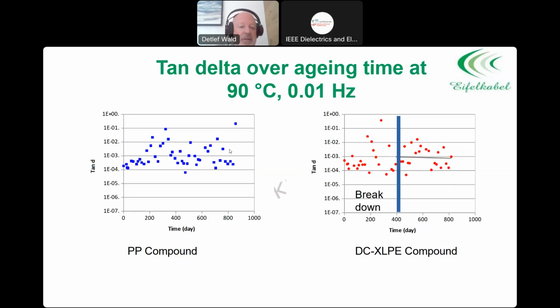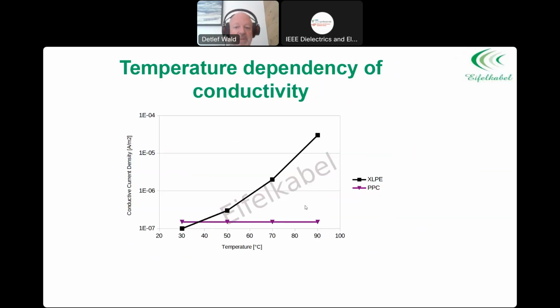About aging, here we measured the tangent delta over time. You can see a big spread, but over aging, because the issue is you are creating carboxyl groups, which are polar, and that means you have an increase in tangent delta. The issue here was also that we had the first breakdowns with XLPE roughly after 1 year and some months in that test. There are new tests set up, and they hopefully will report soon.